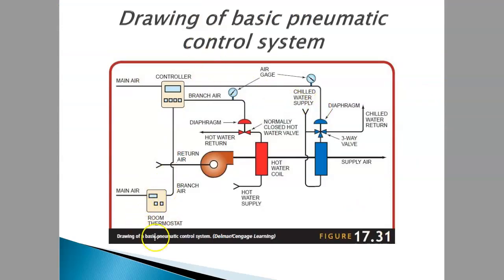Okay, here is a drawing of a basic pneumatic control system. For example, here it has a room thermostat to sense whatever parameters it needs from the room, and then send to the controller. This is the controller. So what is the controller? The controller will sense or control the output, the desired output. So here it controls the valve, a normally closed hot water valve. Normally closed means that when it needs, it will open, because it is normally closed.